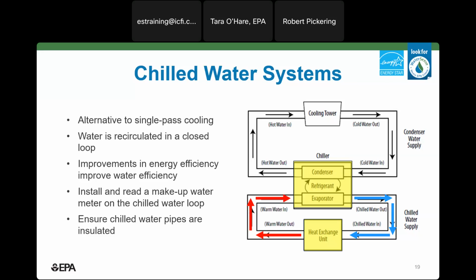So the chiller unit is what generates the chilled water through a refrigeration process. The chiller transfers heat from the chilled water loop to the condenser water loop, which heats the water. And then lastly, the condenser on the refrigeration cycle may be either air-cooled or water-cooled. Larger units tend to be water-cooled using a cooling tower, as shown here. Water is evaporated from the cooling tower. We're not as concerned with air-cooled models from a water efficiency perspective, so we're going to get into more detail on cooling towers now. That condenser unit or cooling tower then cools the water and returns it to the chiller.